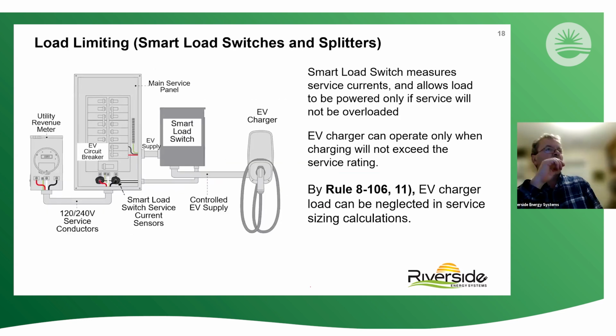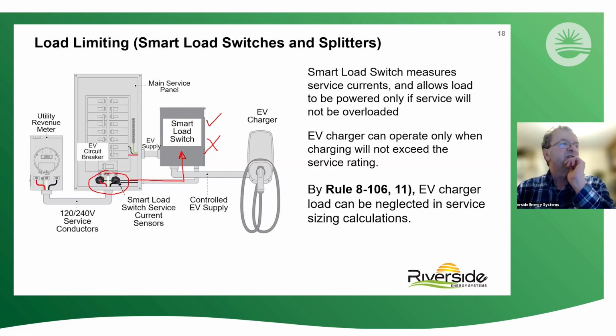So how do these devices work? Well, here's an example of a device that will allow us to eliminate the EV charger from the service sizing calculation. This is a smart load switch which uses current transformers to measure the service demand current and either enable or disable the EV charger based on whether the service has enough capacity left in it at that moment in time. Using this strategy, the EV charger can be scratched off and we don't even have to count it in our service sizing.